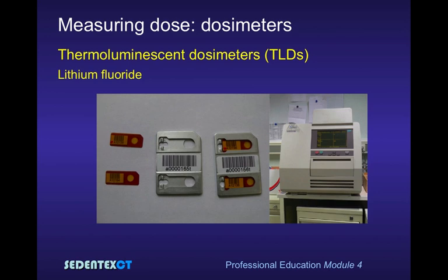So when we want to calculate the effective dose from a particular radiological procedure, we assemble many of these small thermoluminescent dosimeters in the phantom, expose the phantom, usually many times in order to get a substantial amount of radiation built up, and then we analyze each individual TLD and work out first the absorbed dose, then the equivalent dose, and then calculate the effective dose for that procedure. Clearly, in vivo, this could only be used for superficial skin doses. But by using the phantoms, we can get a true indication of effective dose.